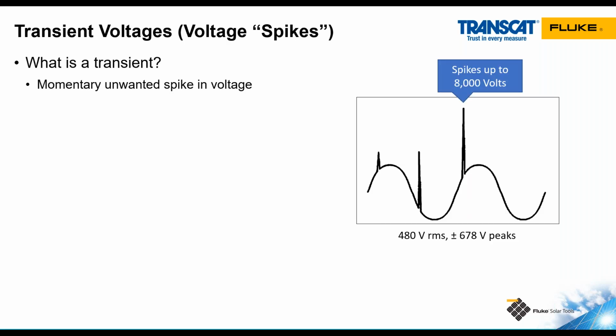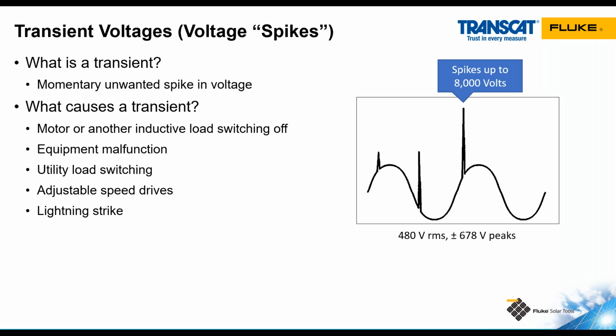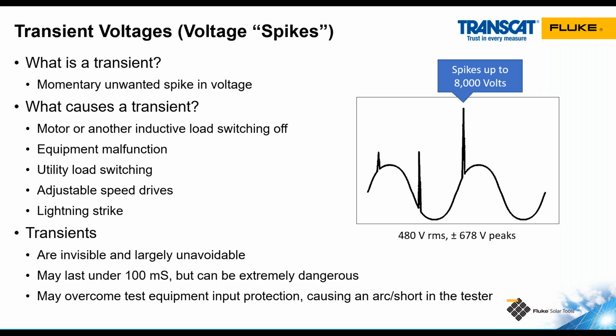When we're looking at selecting our test and measurement equipment and making sure it's properly rated, the first thing we need to learn about is transient voltage spikes. Transient voltage is a momentary spike in voltage that we're not looking for. In the solar industry, it's typically coming from the utility, either from an issue in the utility like load switching or an equipment malfunction. If we have a system that is connected in a commercial building, we could have motors turning on and off, which might be causing transient voltage spikes. And then on the DC side, lightning can cause transient voltage spikes. They're invisible to normal multimeters and clamp meters. We do have at Fluke power quality analyzers that are capable of logging transient voltage spikes if it's a consistent issue that you need to troubleshoot. They're very short duration, but they can be very dangerous.